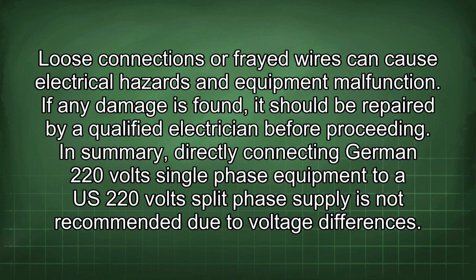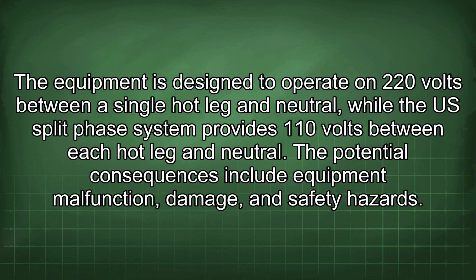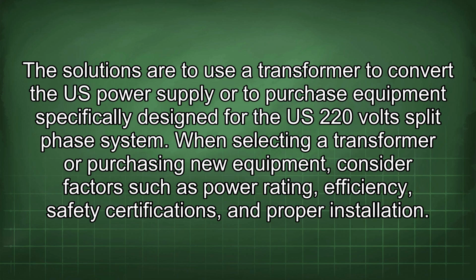In summary, directly connecting German 220 volt single-phase equipment to a US 220 volt split-phase supply is not recommended due to voltage differences. The equipment is designed to operate on 220 volts between a single hot leg and neutral, while the US split-phase system provides 110 volts between each hot leg and neutral. The potential consequences include equipment malfunction, damage, and safety hazard. The solutions are to use a transformer to convert the US power supply or to purchase equipment specifically designed for the US 220 volt split-phase system.